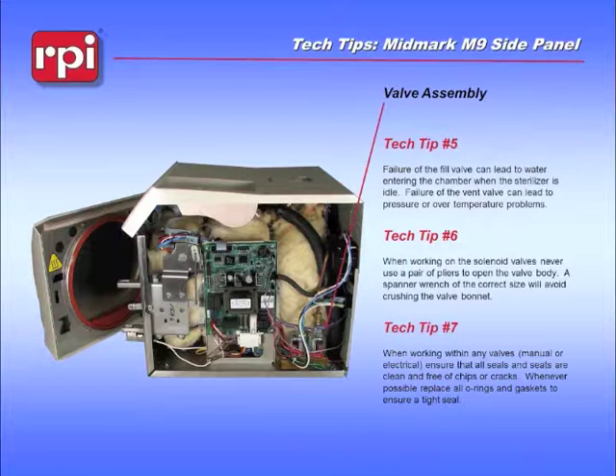Okay, looking at the individual valve assembly on the newer style M9 M11s, and this does apply to the older machines as well. Failure of the fill valve frequently causes water to show up in your chamber when the machine is not functioning. Water leaks past the valve. Failure of your vent valve prevents air from escaping the chamber. The machine won't ever vent properly.